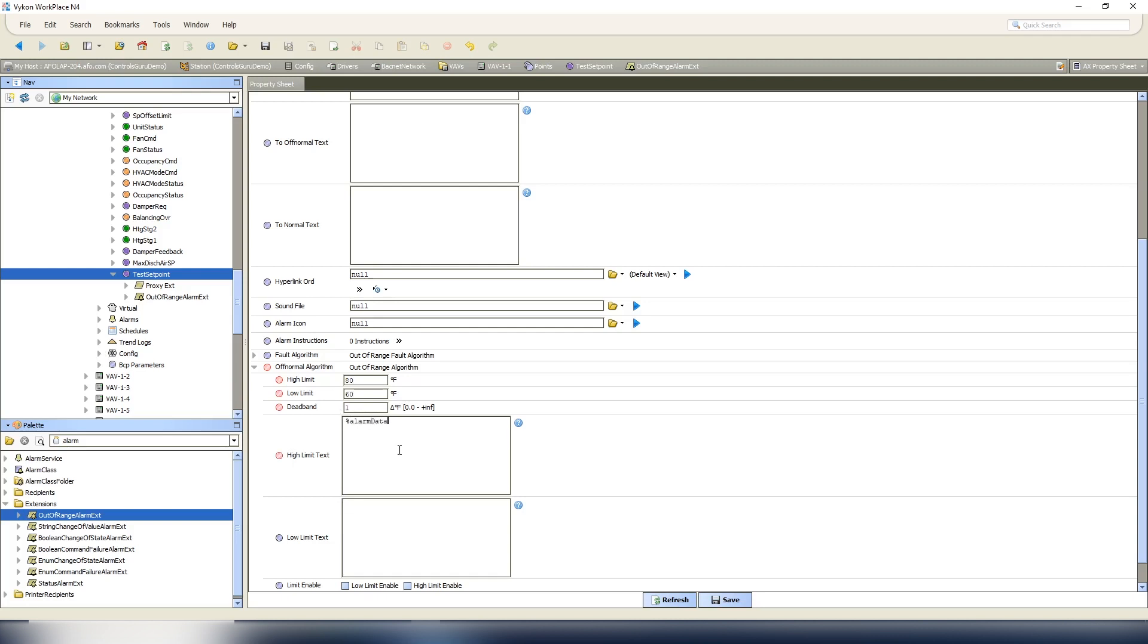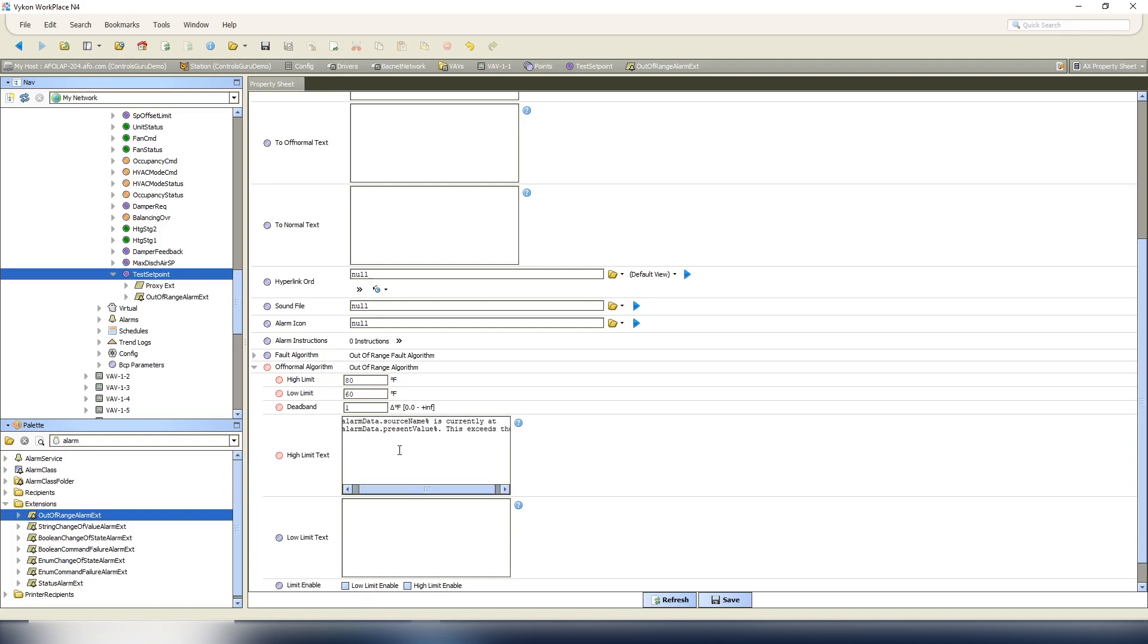So for the high limit text, what we're going to do is alarm data dot source name is currently at, alarm data dot present value period. This exceeds the limits of, and then we can do alarm data dot low limit and alarm data dot high limit.